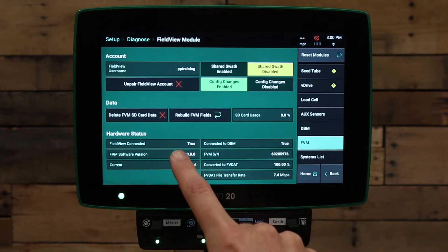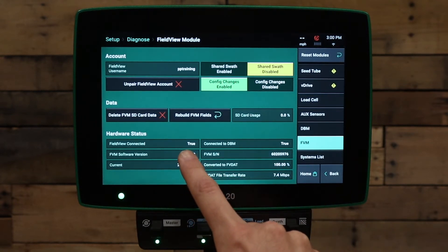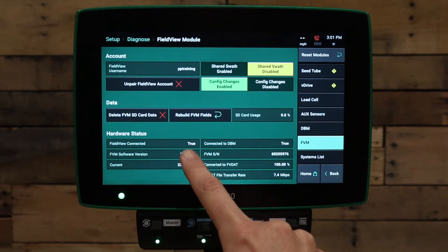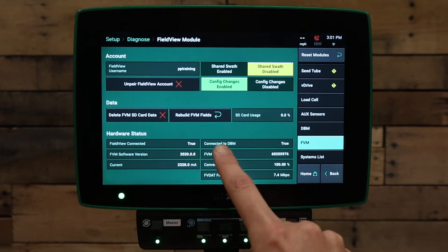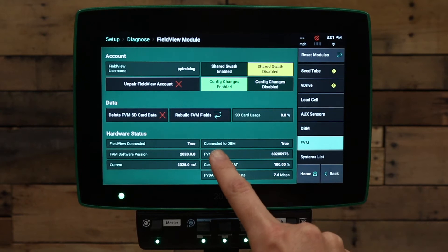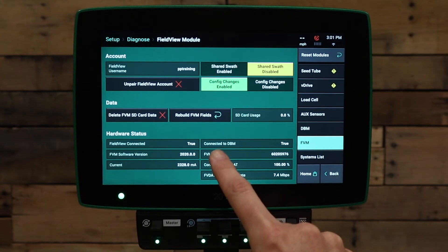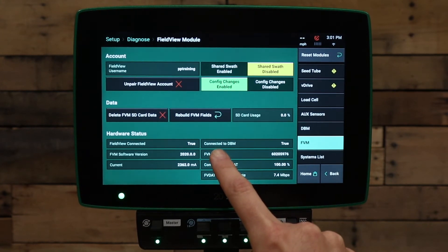Secondly, we have FieldView connected, which says true currently. If this says false while connected to DBM says true, then that indicates that the 2020 is connected and communicating to the FieldView module, but not connected or communicating to the FieldView app on the iPad.